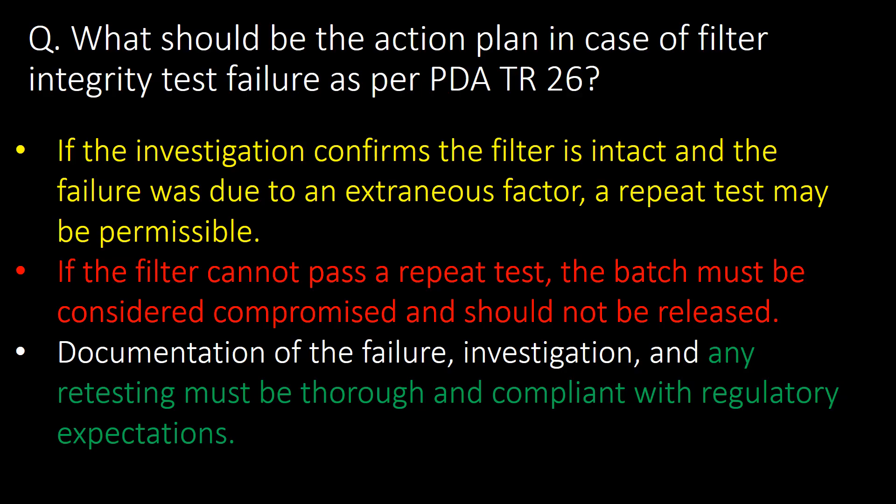What should be the action plan in case of filter integrity test failure as per PDA's Technical Report No. 26? If the investigation confirms that the filter is intact and the failure was due to an extraneous factor, a repeat test may be permissible. If the filter cannot pass a repeat test, the batch must be considered compromised and should not be released. Documentation of the failure investigation and any retesting must be thorough and compliant with regulatory expectations.